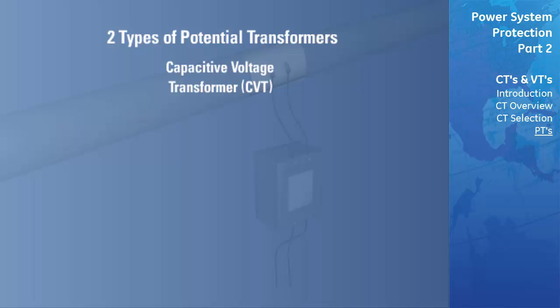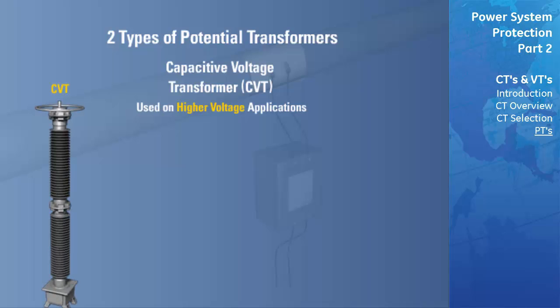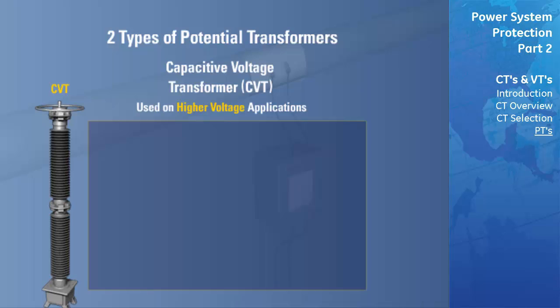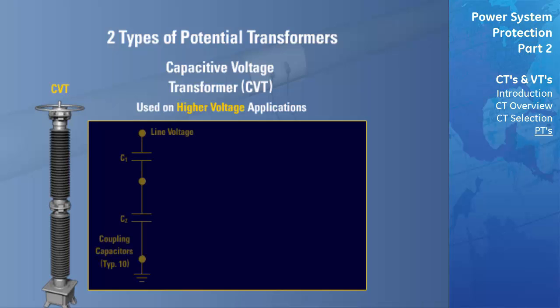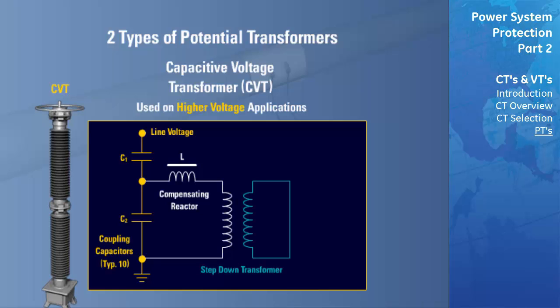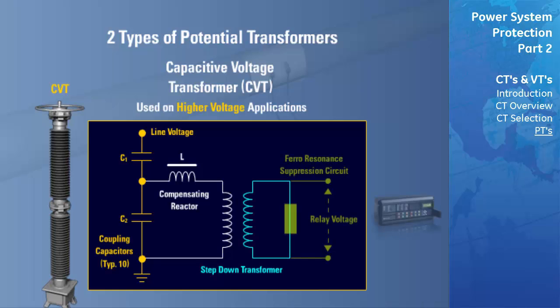Capacitor voltage transformers, or CVTs, are normally used on higher voltage applications. The CVT is basically a capacitance potential divider and consists of the following components: coupling capacitors, typically 10; a compensating reactor; a step-down transformer; and a ferro-resonance suppression circuit that is found just before the output terminals for connecting to a relay.